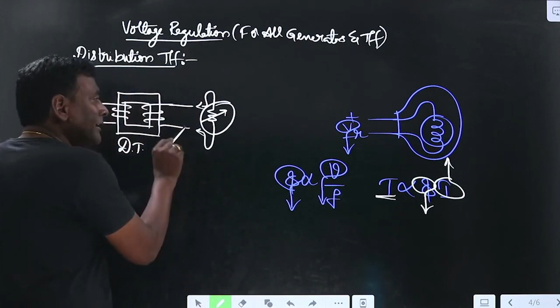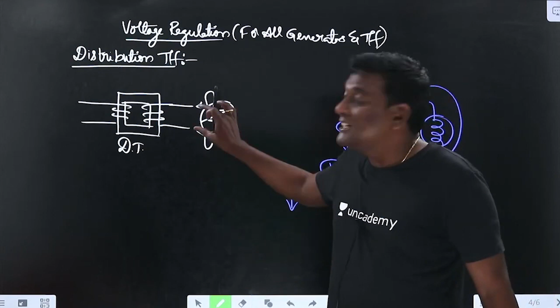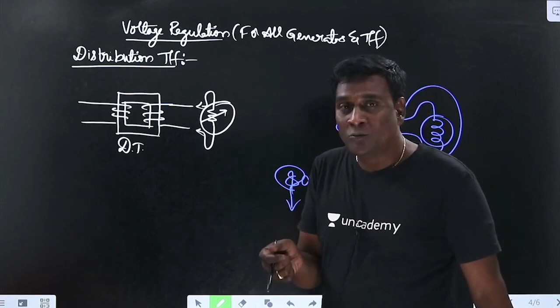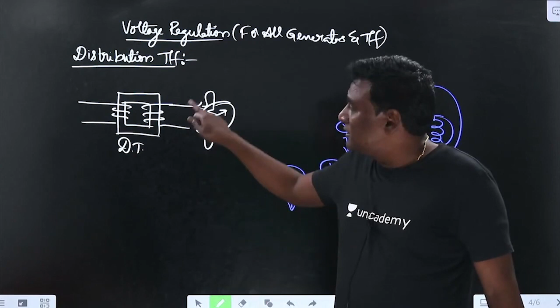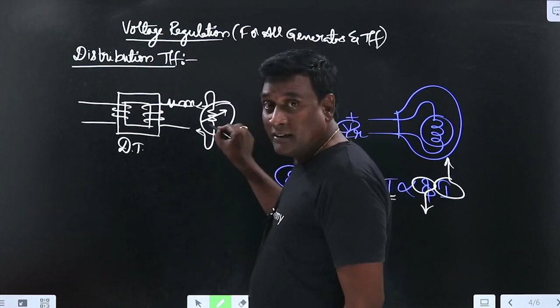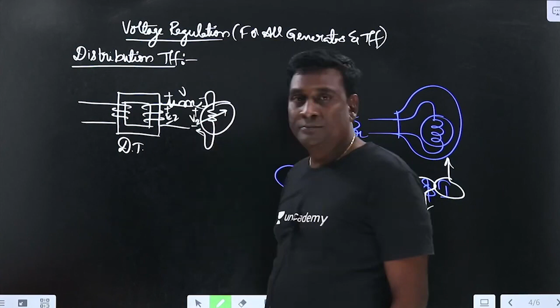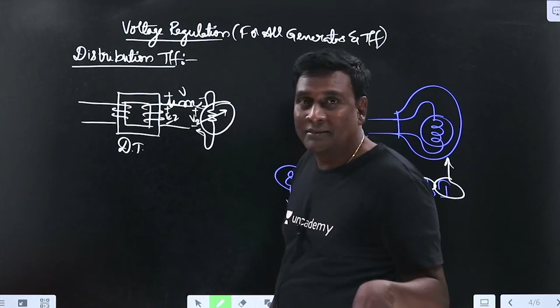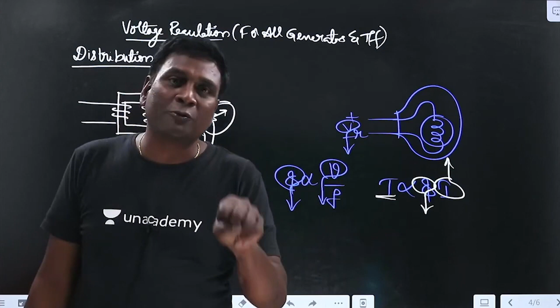Okay, see here, my distribution transformer is supplying power to all utilities, and all utilities' performance will be severely influenced by whether the voltage profile is maintained or not. Now what is the need, what is the purpose of defining voltage regulation? Because for my transformer I am going to have internal resistance and internal reactance. Now the moment it is loaded, automatically voltage drop will happen here. So E2 will be there here. E2 minus this particular voltage drop is going to be the terminal voltage V2. Now depending upon terminal voltage variations, all of my utilities' performance will be severely influenced. That's why voltage regulation is very much important for a distribution transformer.